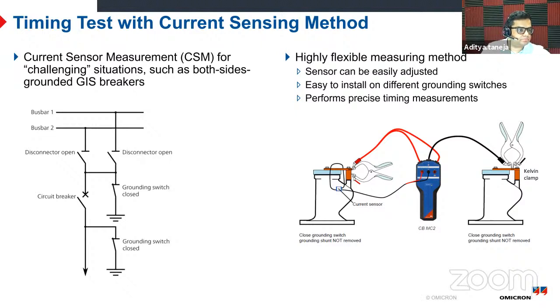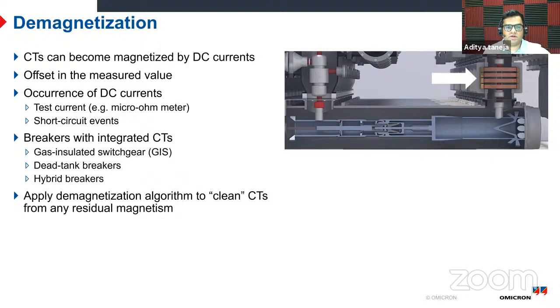So yeah, this is something which is quite useful for GIS. Okay, and the other challenge with the GIS is that there are CTs inside the current path. So when we are injecting through the ground loop, CTs are there, which also get the DC current in the primary circuit, and that can cause some kind of residual magnetism in the CTs, which we need to clean. And sometimes it is not easy to open the CT secondary box to clean them. So if we can clean this residual magnetism with primary injection itself, that would be great.